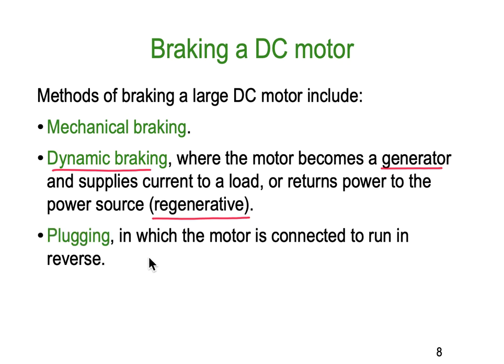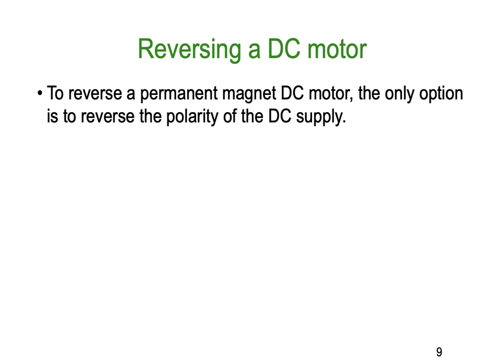Plugging is where the motor is simply connected to run in reverse. The motor is running in one direction and you switch it into reverse, which puts the brakes on big time. But you've got to have a supply capable of providing very large currents. To reverse a permanent magnet motor, the only option is to reverse the polarity of the supply — because the permanent magnet doesn't reverse, you're only reversing the armature relative to the fixed magnetic field.